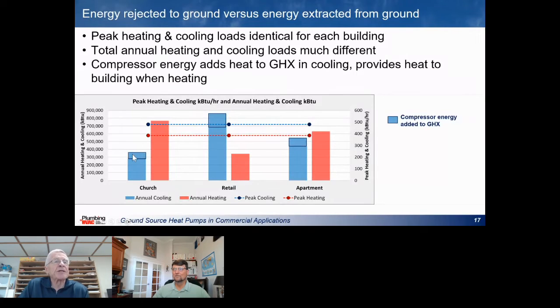And it gets even worse because the compressor energy, the electricity that you're using to power the compressors and pumps, is going to go into the ground heat when you're air conditioning. The compressor is cooled by the refrigerant. That heat is going to be dumped into the ground, and it's also going to supply some of the heat to that building when you're heating that building. So you're extracting less heat from the ground than you're delivering to the building. You're dumping more heat into the ground than you're taking from the building.